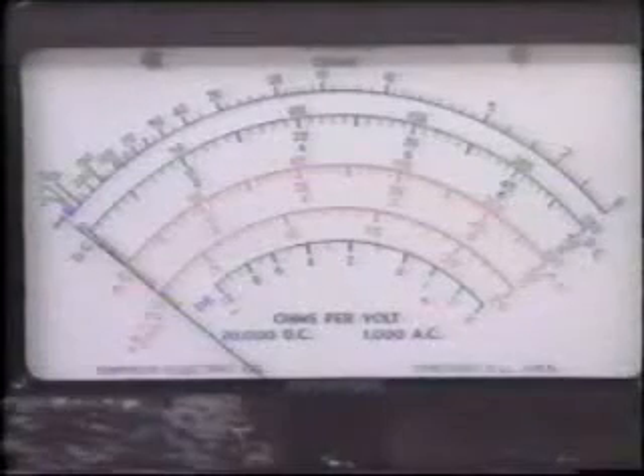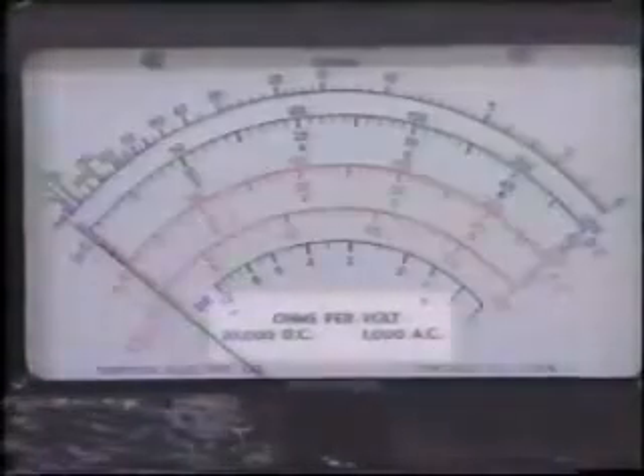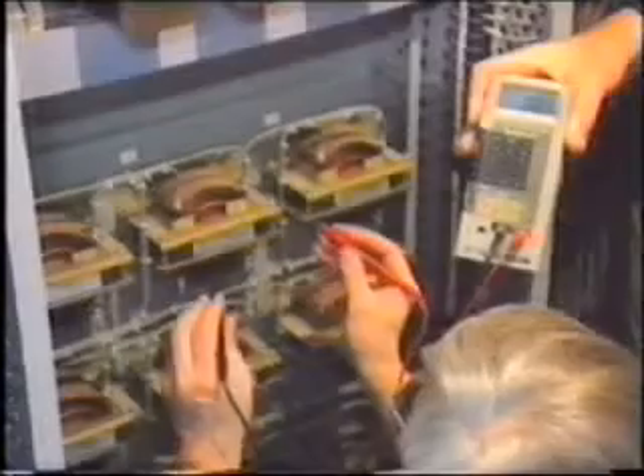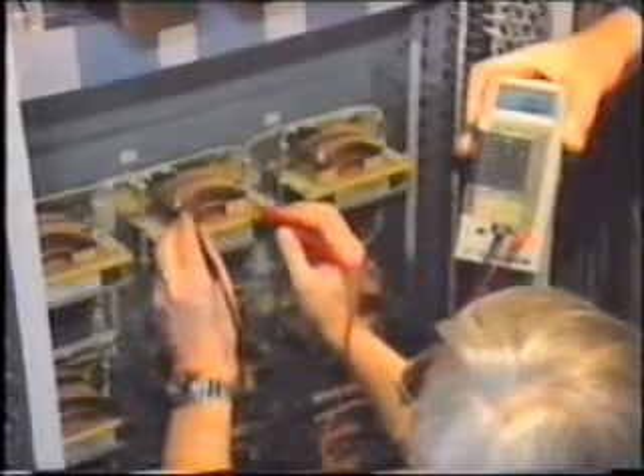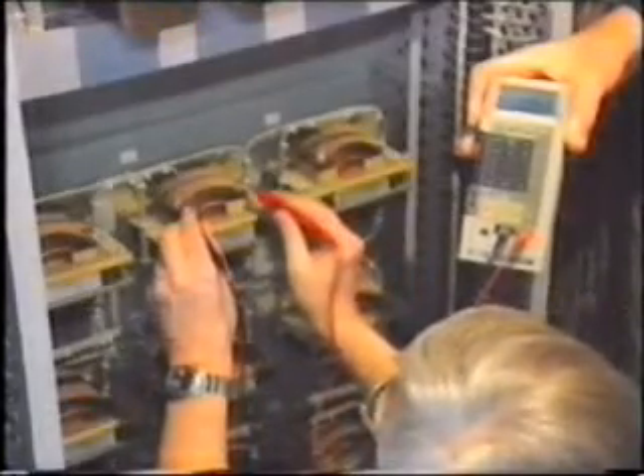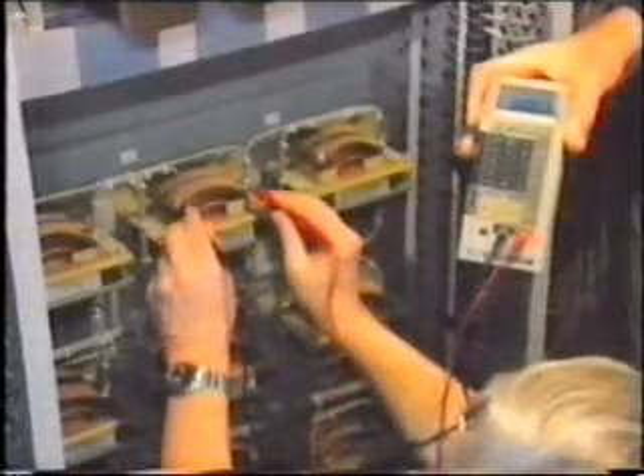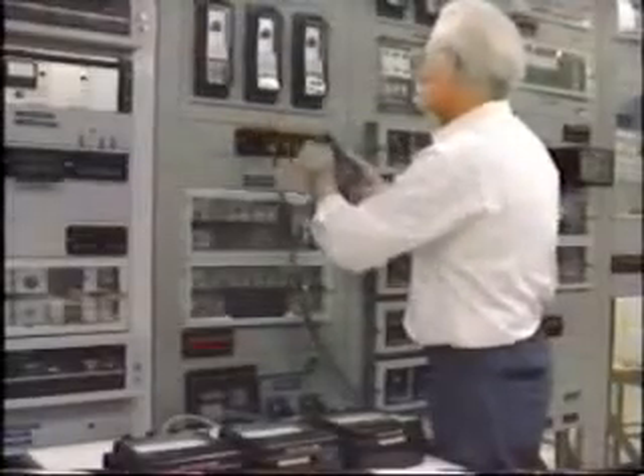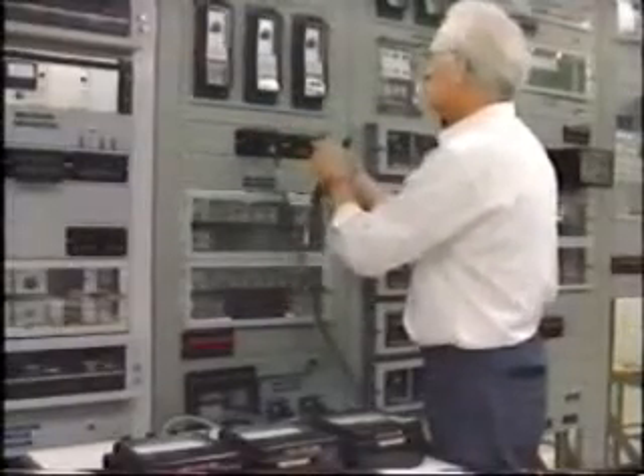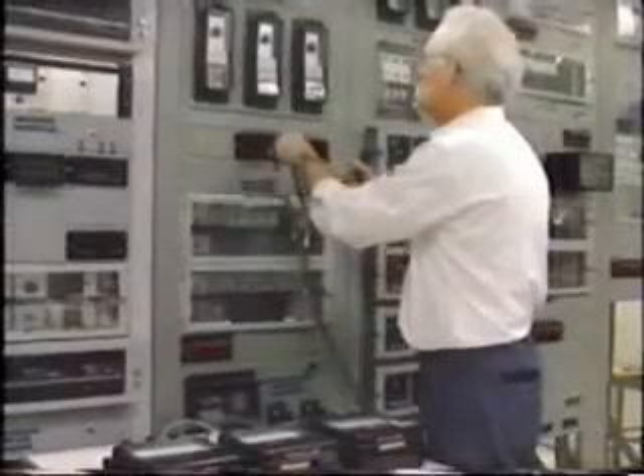However, be aware of this problem when using an analog meter of lower impedance. It is good to remember that no circuit remains undisturbed when taking readings. When measuring currents in this live circuit, analog ammeters with less than 1% error are being used. Multimeter use is not recommended in this situation.